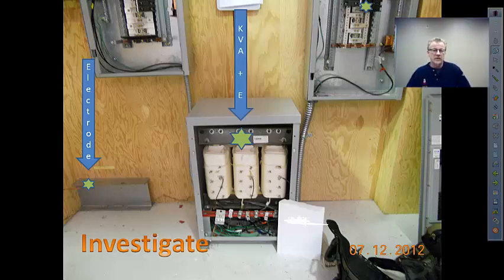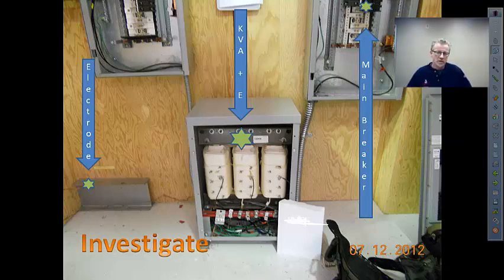Transformer kVA and voltage need to be determined, either from the nameplate or from the blueprints. Also, whether it's a three-phase or single-phase. Whether the secondary is Y or delta would come into play, possibly or certainly, in your sizing of the neutral conductor, if any. Lastly, the overcurrent protective device, or the rating of the device which is being fed by the transformer, depending on which tap rule we're using.